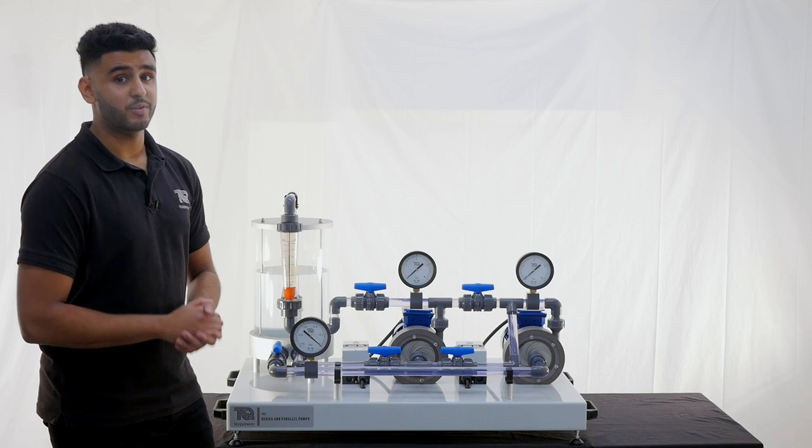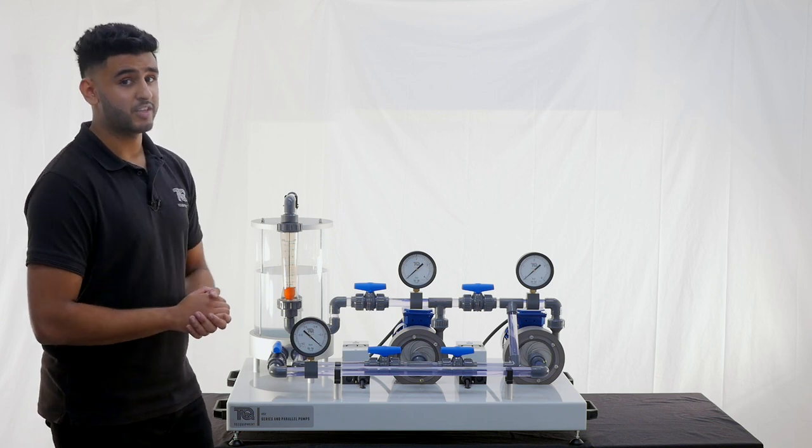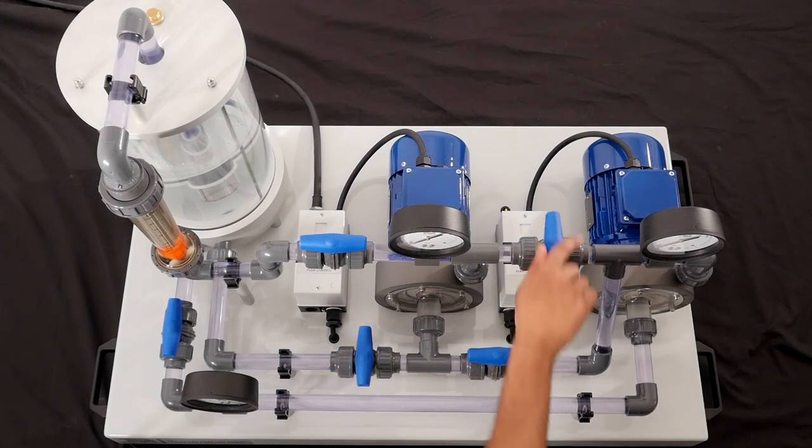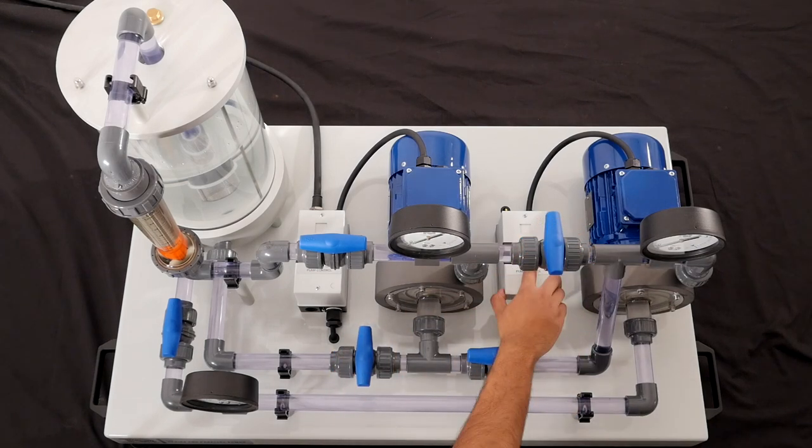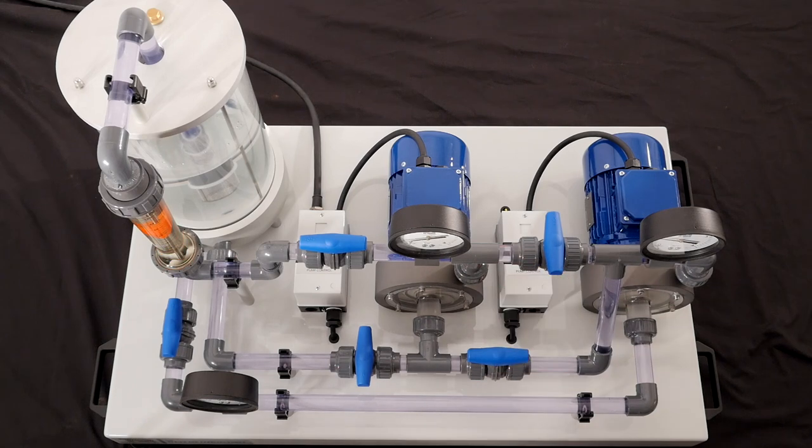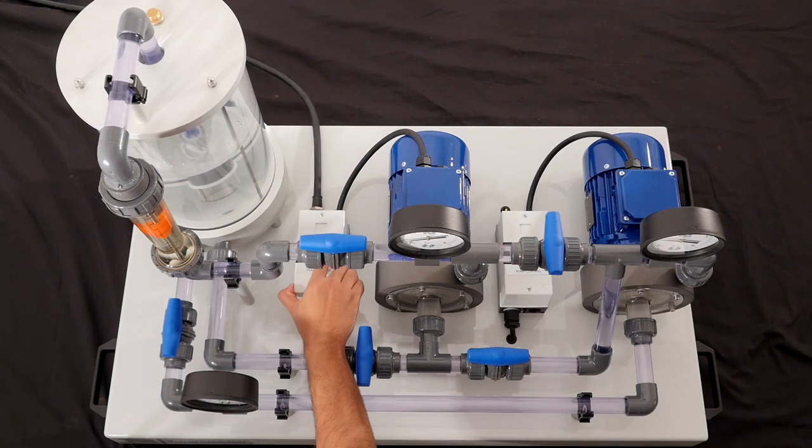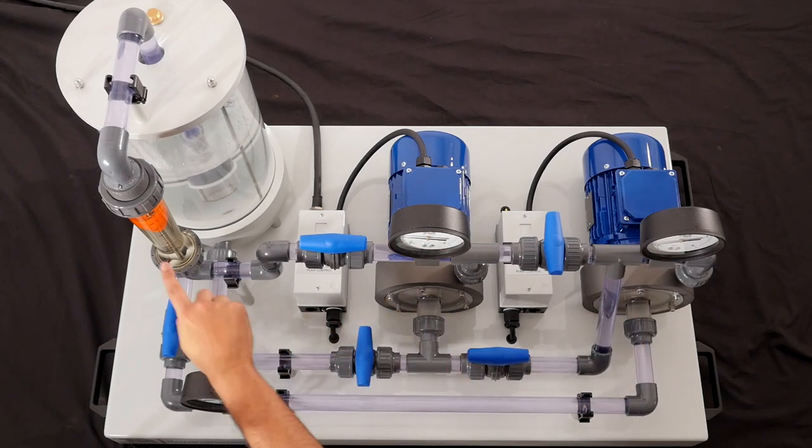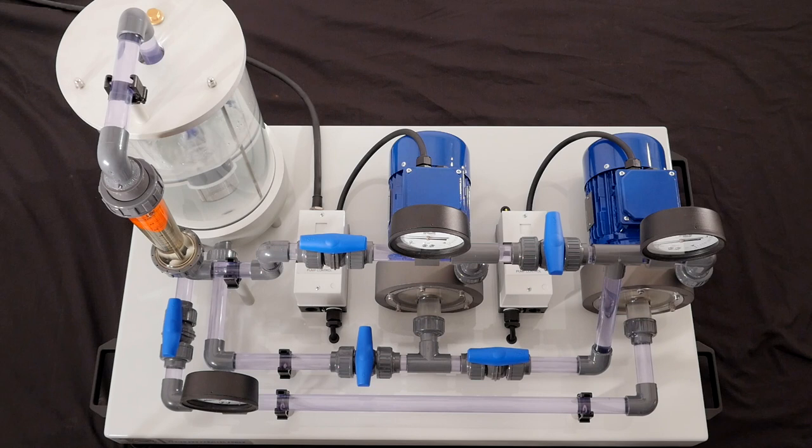As I mentioned before, the adjustable valves allow a wide range of pump configurations. To run the unit in series, you first close these two valves, turn on pump 2, and then pump 1. Water will be drawn from the reservoir through to pump 2, using pump 2's outlet as pump 1's inlet, and then back to the reservoir. For two identical pumps in series, the head will be twice the head of a single pump at the same flow rate.